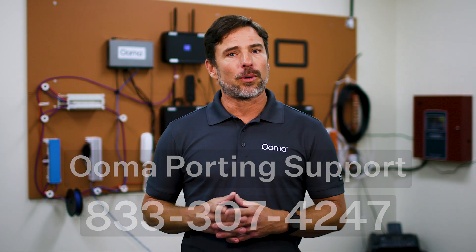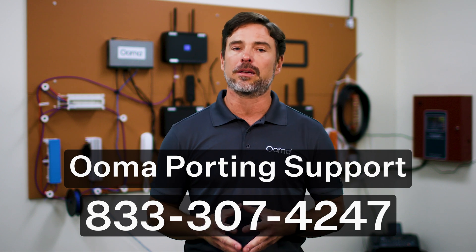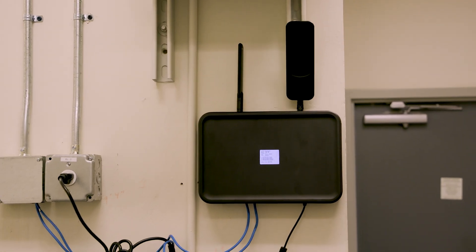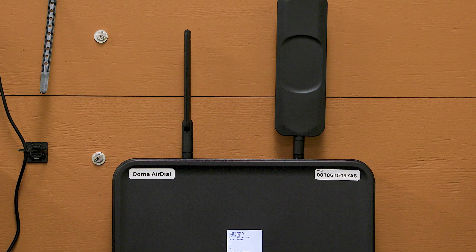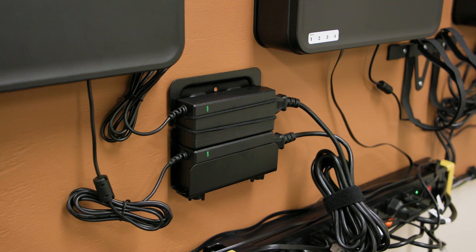If porting numbers, call Ooma support at 833-307-4247 and provide the master ticket number from the work order. Porting can take up to 14 days to complete. In some cases, the porting will be coordinated in advance to happen at the same time as installation. If equipment is cut over from POTS to AirDial before the port is completed, and the equipment needs to receive calls from the number being ported, set up a forwarding rule on the old POTS line to forward all incoming calls to the new AirDial number. Once you have confirmed successful operation of equipment connected to AirDial, you can mount the AirDial unit. Try to maintain a distance of at least one foot between AirDial and other electrical equipment or metal devices. Ensure that nothing is touching the antennas and that they are oriented vertically. Ensure that there is no weight on the AC connector cord. Mount the AC adapter to the wall if necessary.